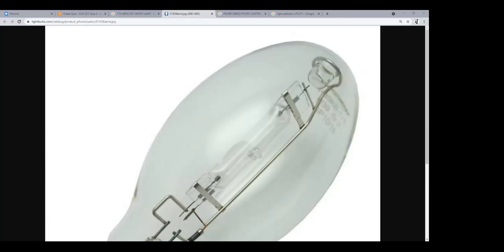That's a mercury bulb right there. Yeah, you can tell just by the shape of it, can't you? You're a professional. That's right. And the leads that you see on both ends, when you've got 120 going to a light, and we're not going to go into too much detail on this, does everybody remember what a ballast does? And a capacitor? Well, a ballast is a momentary transformer. You're going to have about 400 volts going into this thing to ignite it. Then once it's ignited, it's going to burn. So the two ends are going to ignite the gas in here. I don't know if it's hard to see on your screen, but on the lower side right there, you see that kind of more grayish area?